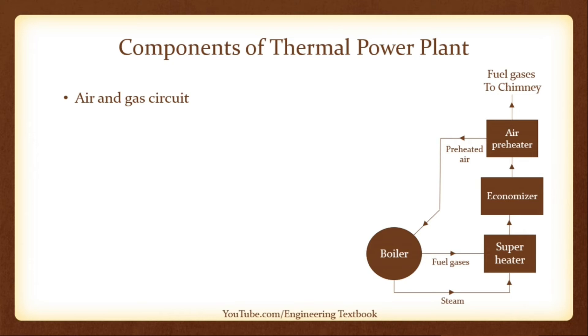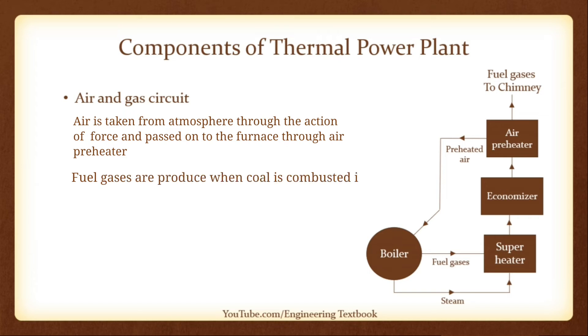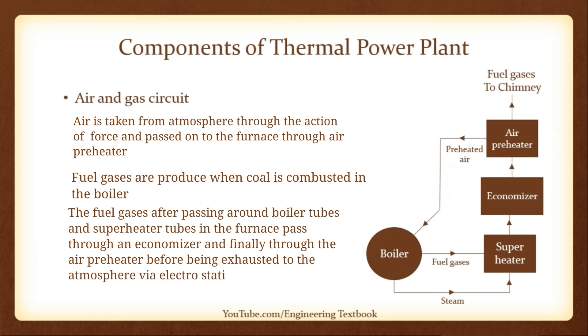Air and Gas Circuit. Air is taken from the atmosphere and passed on to the furnace through an air preheater. Flue gases are produced when coal is combusted in the boiler. These flue gases, after passing around the boiler tubes and superheater tubes in the furnace, pass through an economizer and finally through the air preheater, before being exhausted to the atmosphere via an electrostatic precipitator and chimney.